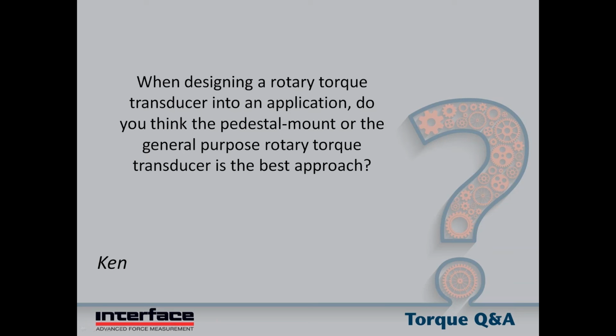So the danger with the pedestal mount or a foot mount sensor is some customers or applications may tend to want to use that as a bearing block, but you definitely don't want to wear the bearings out in the torque sensor. So if there are going to be bearing loads, you need to make sure they're taken by bearings that are intended for that purpose, such as pillow blocks or jack shafts, whatnot.